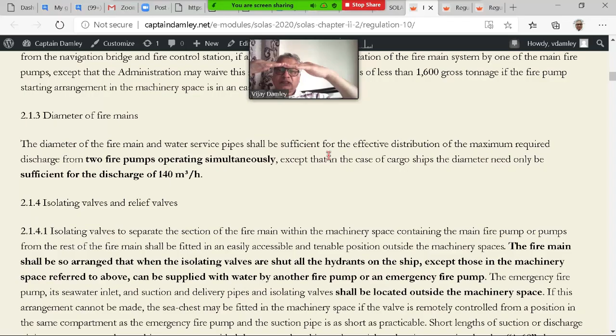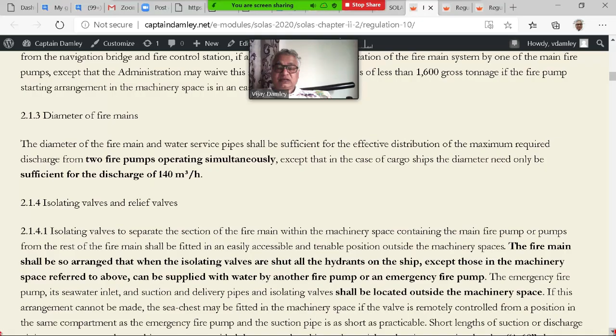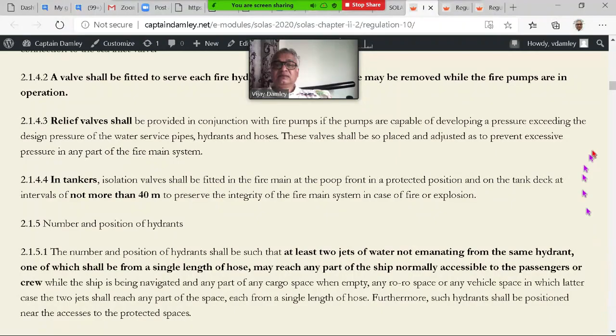So coming down again to this, the relief valves, isolating valves, all are on deck, outside machinery space. Okay, this is important, outside machinery space. Then, like I told you, the hydrant, there is a valve fitted, otherwise how will you close the hydrants? Now on ships, each and every hydrant will have a valve. And when you say take pipelines and all, the many pipelines which are used ashore, they have openings but they don't have valves. Why? Because it is expected you start the pump and it has to be open. So they don't fix the valve, they save the money. On ships, every hydrant will have a valve and a coupling.